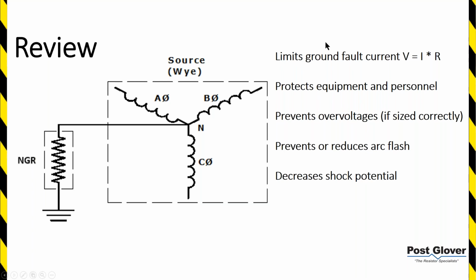So it does, like I mentioned before, limit the ground fault current using Ohm's law. And all you need to remember is that resistance is inversely proportional: as the resistance goes up, the current goes down. It does protect equipment and personnel. The lower current you have, the more it does that. Just as an example, for a low resistance ground, you're usually tripping within a fairly quick time frame, and you're trying to limit the amount of damage based on the time exposed and the current exposed as well.